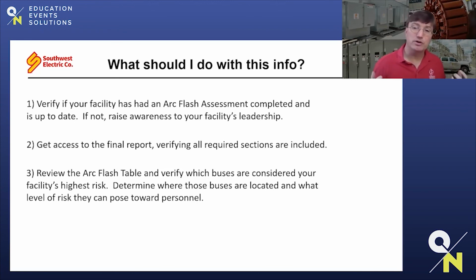And you want to make sure that all the sections are actually included in that assessment, including recommendations for mitigating that arc energy. If you do not have recommendations on how to mitigate arc energy and you have high levels, especially those over 40 calories, I highly recommend you do not live with those energies. Reach out to a contractor who is experienced with mitigation and ask them for the recommendations. Most of the time, their assessments and their quotations are free and something you can consider budgeting around.